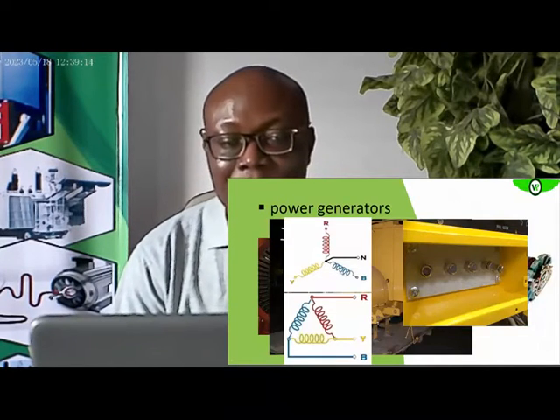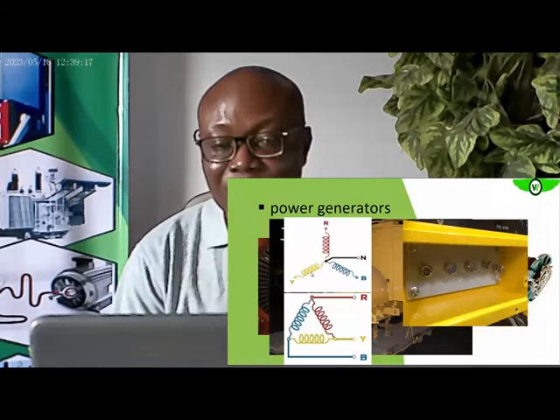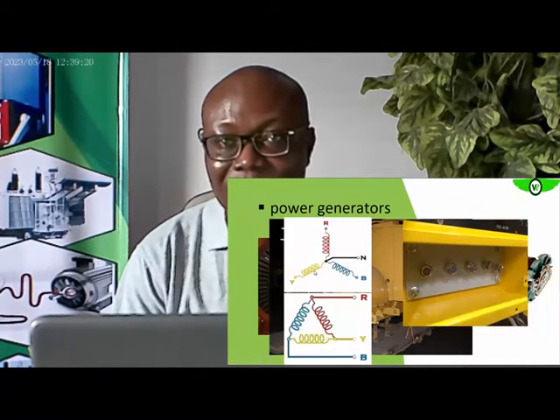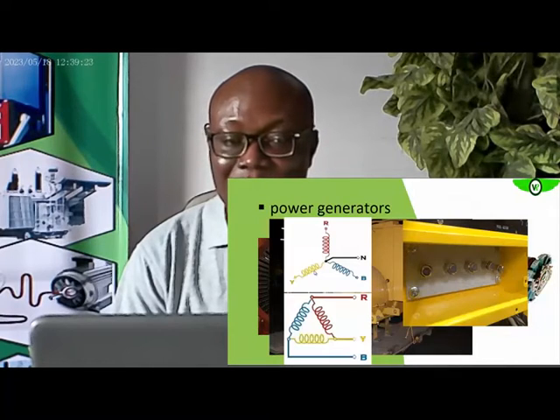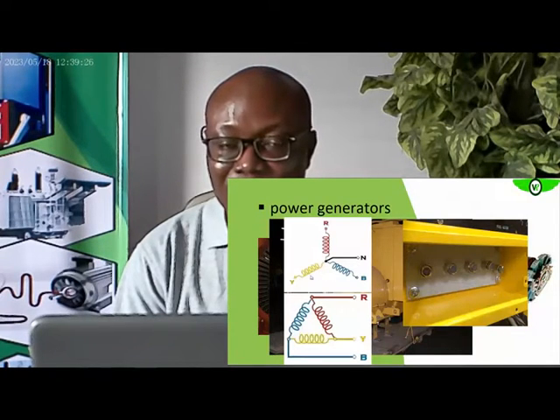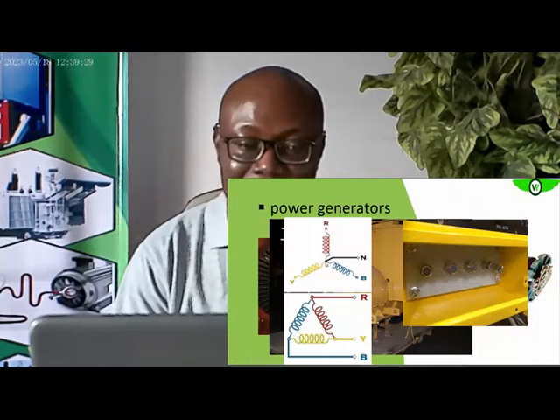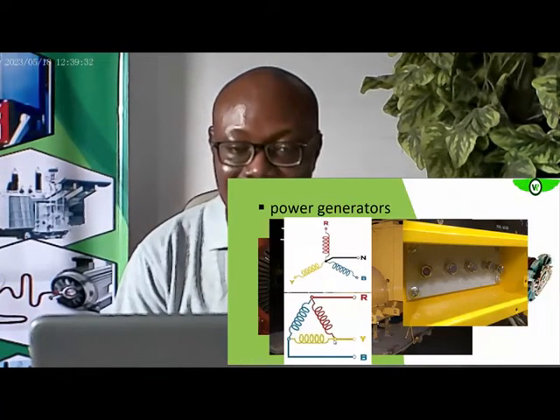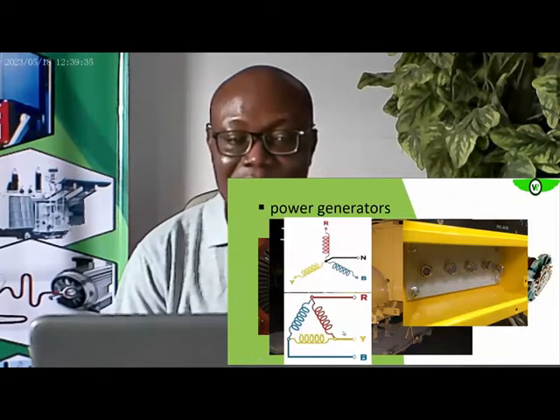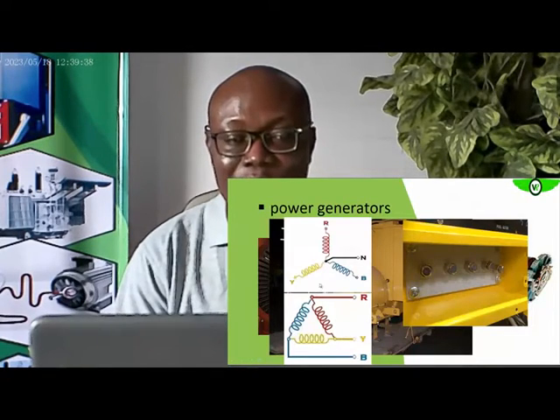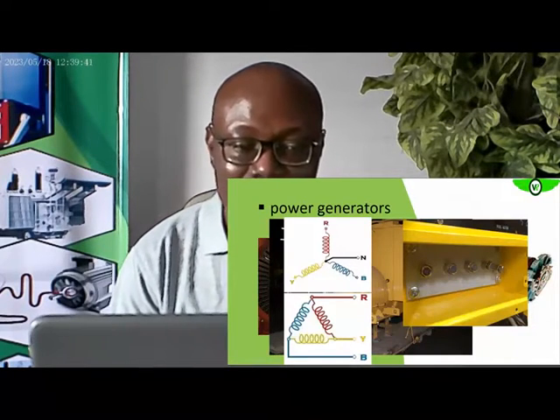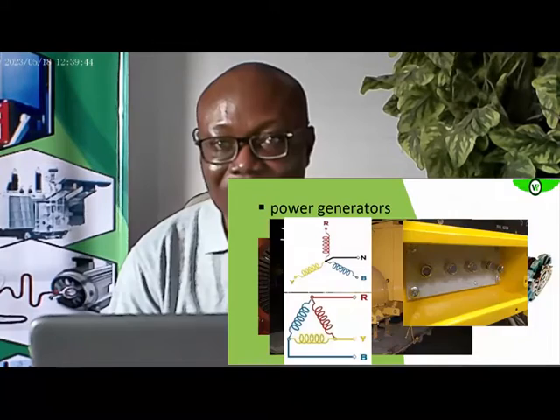So maybe you have a drop in your insulation resistance value. You can now go and open up the connection point. Usually they are brought out to the terminal block inside the generator. Then you can disconnect the star point and test each of these windings to ground to know precisely which winding is shorted to the ground, where you have the problem. Okay, that is it for those three electrical assets or machines.